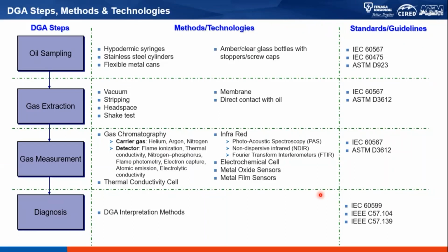These are some of the practices or equipment used, but I believe some of these are quite obsolete. For example, they used flexible metal cans, perhaps mentioned in IEEE C57.104 in 1978, but I don't think it's mentioned anymore in the 2019 issue of C57.104. So it is always recommended, if you want to do DGA, to use syringes, because we can protect the oil, or most importantly, the gases inside the oil, from being released to the atmosphere. Because of that, the results could be deviated and not correct.